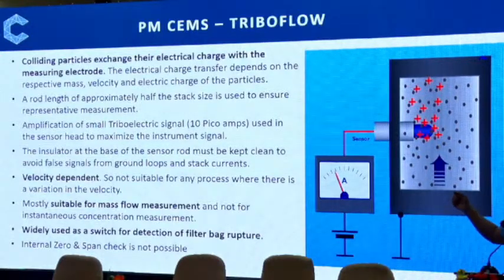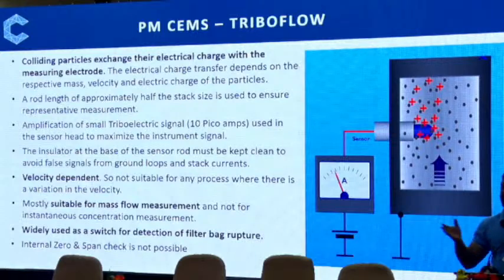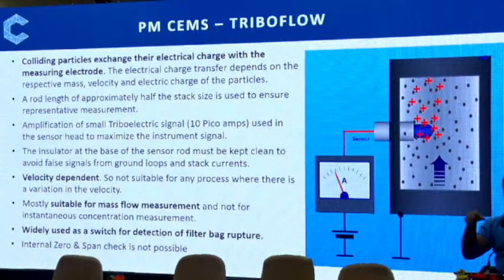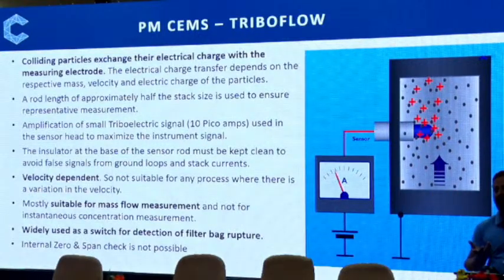Now the problem is if that dust is coming, it is not carrying any charge, and it is not being captured in the ESP either. That is why it is resistive. Indian coal has this kind of property, which is why our emission is higher. So if dust doesn't have any charge, even if it collides with that specific rod, it may not generate a charge because of the particular dust quality. In that case, emission has happened, but you do not get any reading.